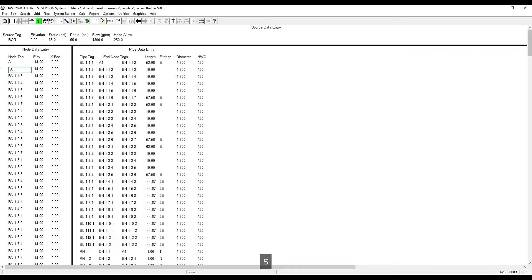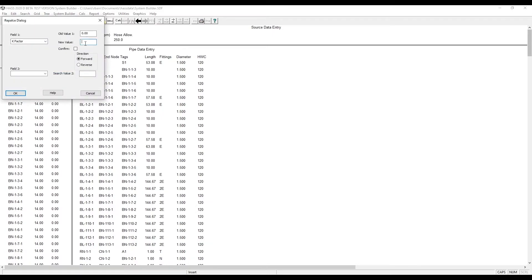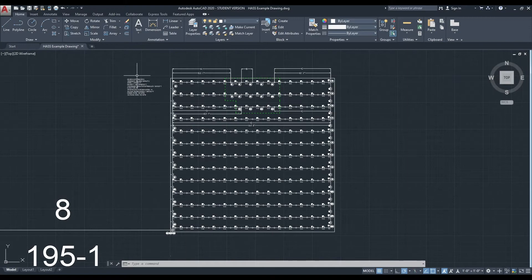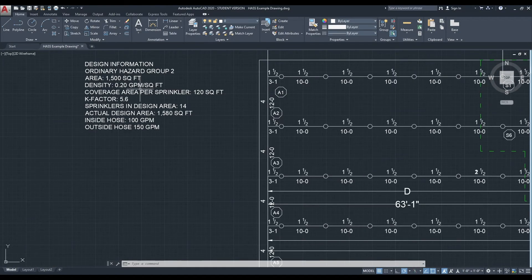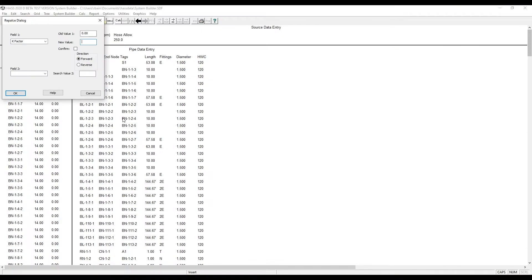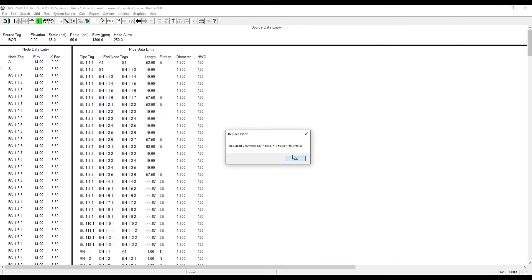Since this is a sprinkler, it's S1. And we need to enter the K factor. The easiest way to do this is replace. Then we're going to use 5.6 for our K factor and replace all the fields going forward.